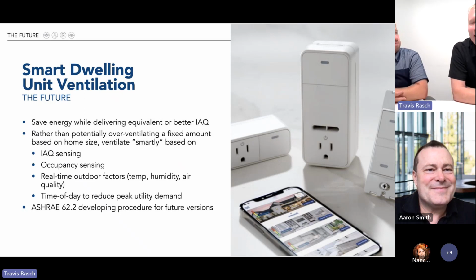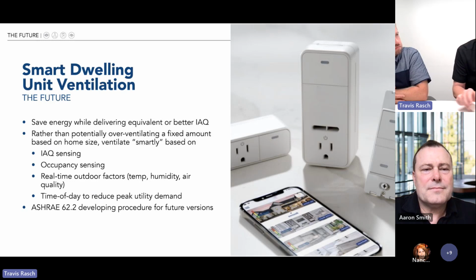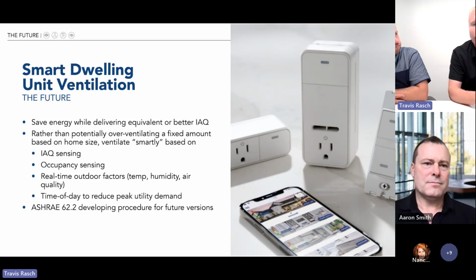I think the latest and greatest, when you look at the latest version of the energy codes—Travis can jump in here—it's all about ERVs and the efficiency of the ERVs, and what's the SRE level. States like Washington, for instance, not only want you to put in the ERV, but you get extra credit points if you put in one with an SRE level of 75 or 85 and so on. So I think the holy grail is to do it smartly, sensing all these different things. Different cities or states have different utility rates at different times of day. Let's ventilate more in the middle of the night, when the coal plants aren't running to support everyone's air conditioners in the afternoon. Again, it's about getting things like ERVs to be as efficient as possible, and states and cities are starting to award energy bonus points for that.